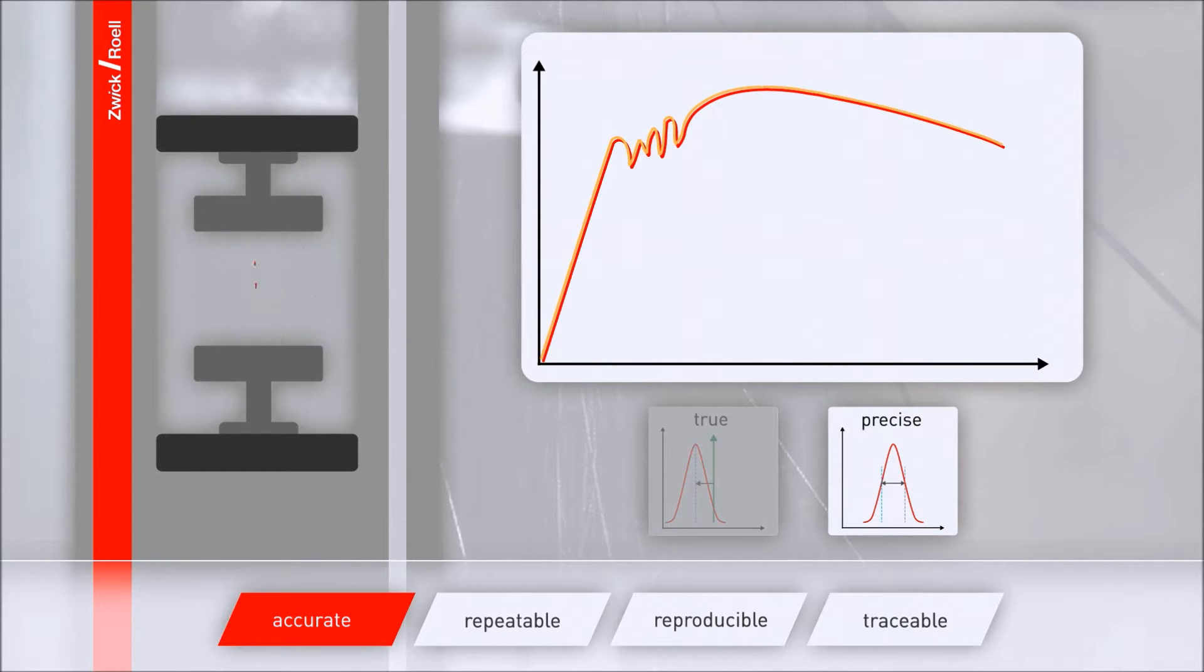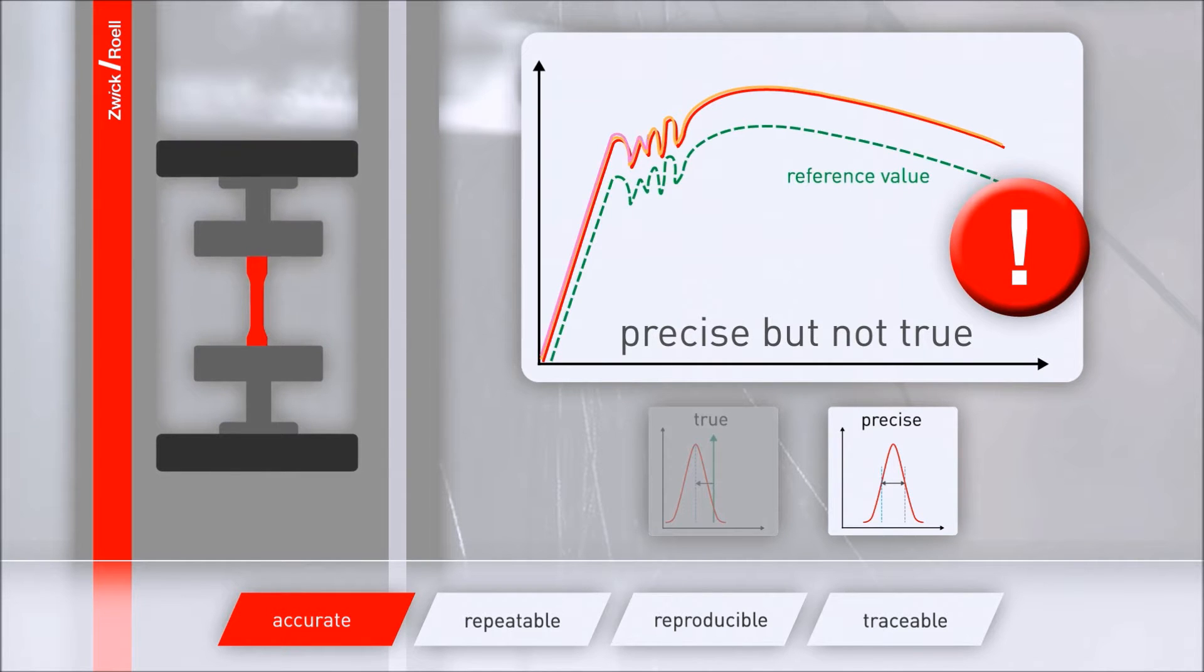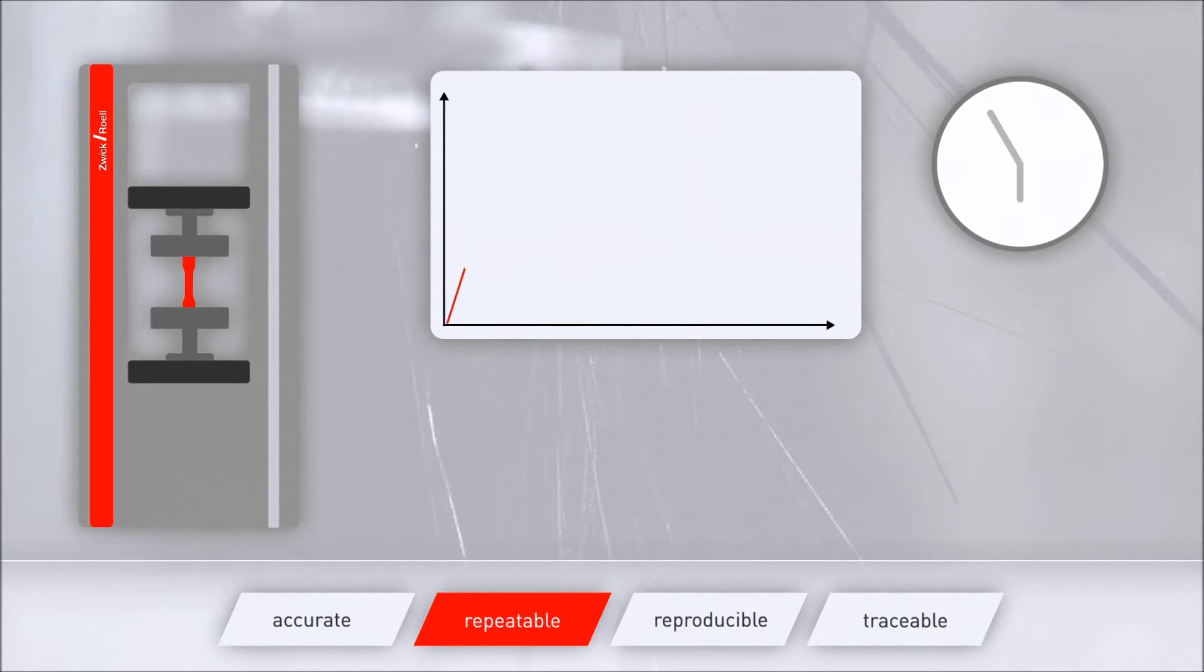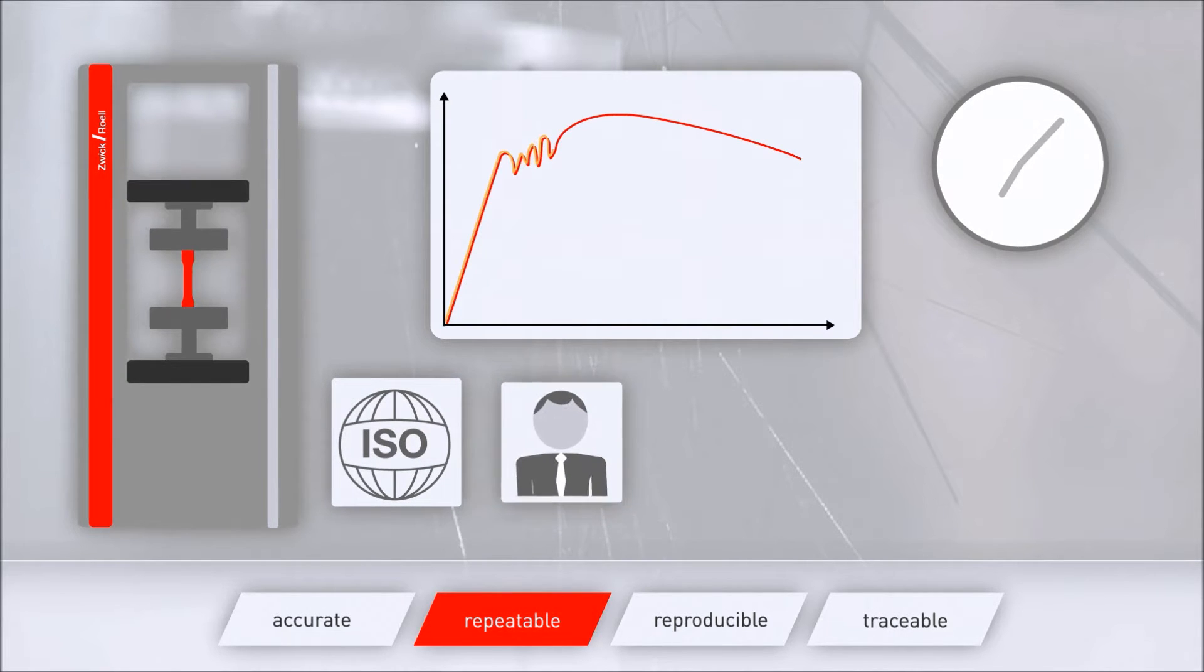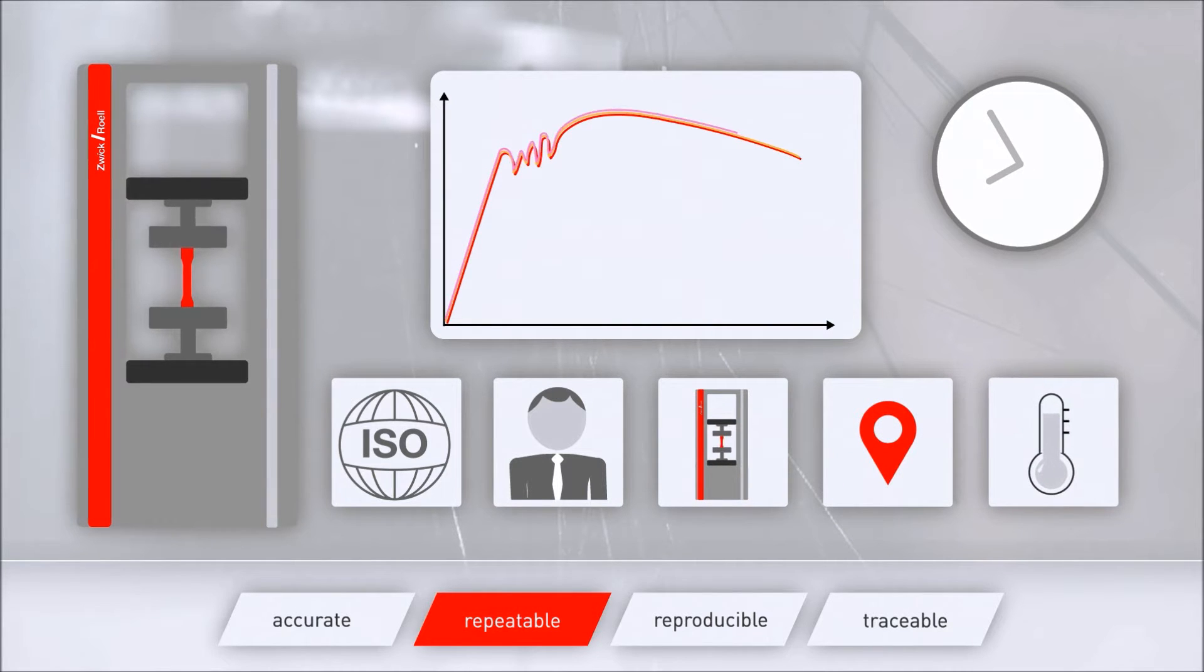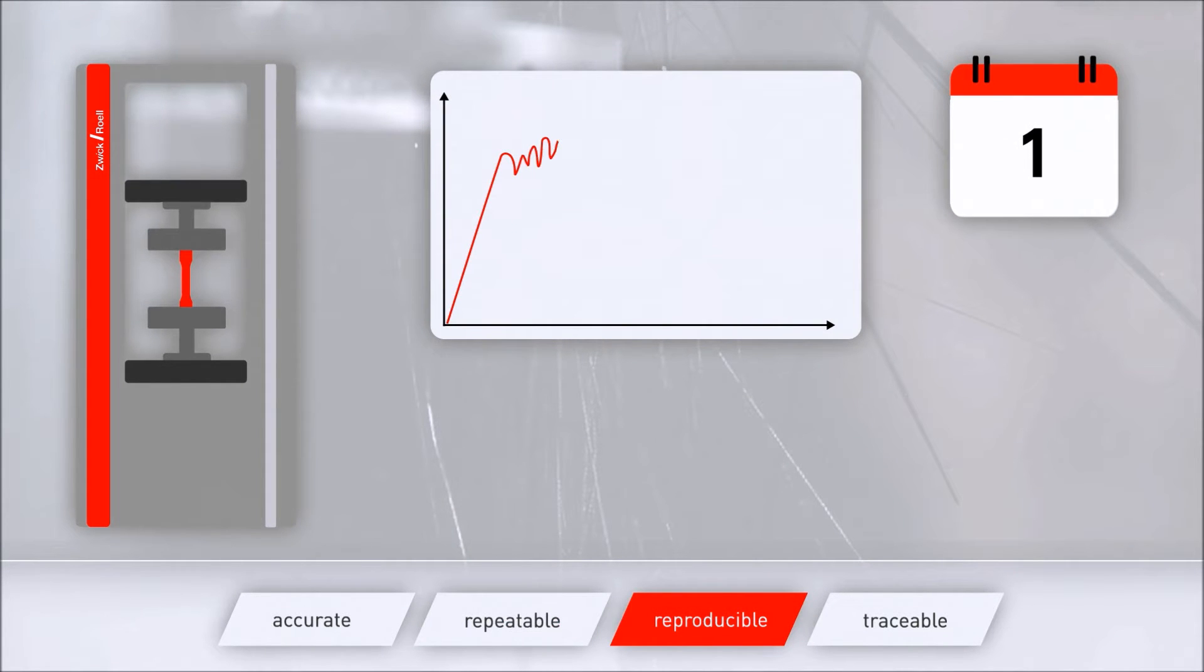However, this still does not mean that the values obtained by measurement are also true. They can be precisely untrue, for example due to systematic error. Repeatable is precision under repeat conditions. This means the same measurement procedure, the same operator, the same measuring equipment, the same location, and the same test conditions. The repetition of measurements within short intervals of time is the only variable factor.